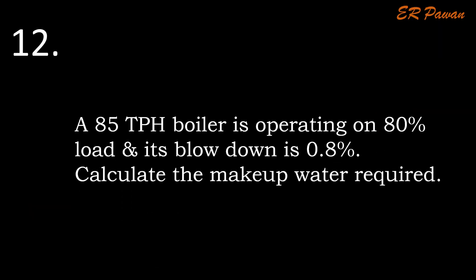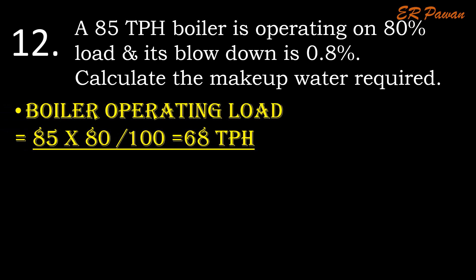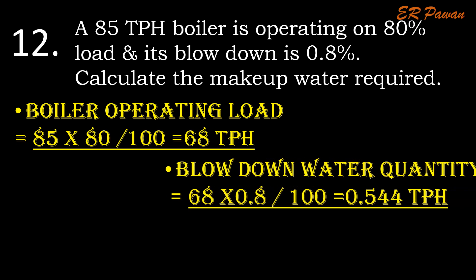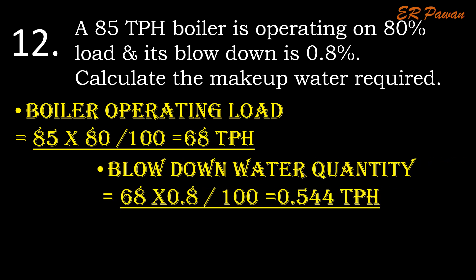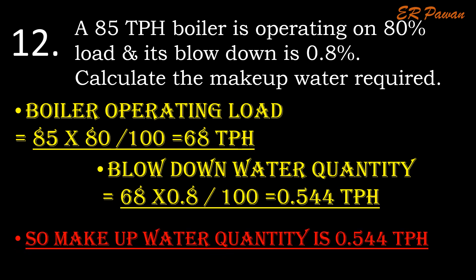Question 12: An 85 TPH boiler is operating on 80% load and its blowdown is 0.8%. Calculate the makeup water required. Boiler operating load = 85 TPH × 80% ÷ 100 = 68 TPH. Blowdown water quantity = 68 TPH × 0.8 ÷ 100 = 0.544 TPH. So makeup water quantity is 0.544 TPH.